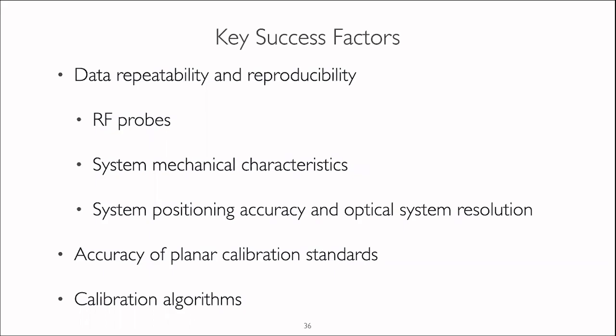If you have good probes but a loose system, and you cannot position the probe at the same point of contact every time you need to measure your device under test, this will significantly reduce the accuracy of your measurements and the accuracy of your calibration. The system positioning accuracy is usually given by the system design, the optical system resolution, the stability of the positioners, the stability of the probe arms, and the cables you use. This is all in total. It sounds very simple, but there is a lot of expertise and understanding behind the system, which provides you with stable and repeatable data.